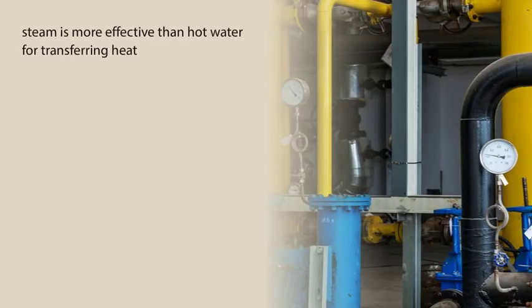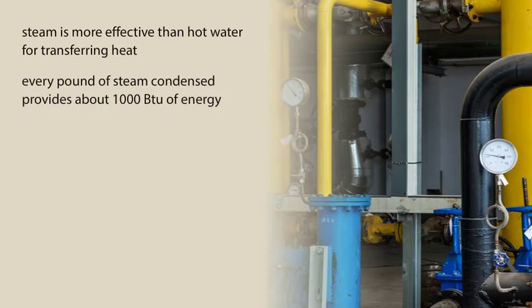Steam is a much more effective means than hot water of transferring heat. Every pound of steam condensed provides about 1,000 BTU of energy. In hot water systems, one pound of water provides only about 20 BTU in a recirculated system with a 20 degree Fahrenheit design temperature drop.